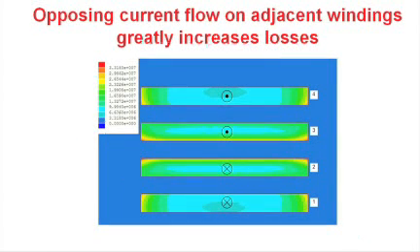However, the situation gets a little worse as you start adding layers of conductors. In this diagram, we're showing two conductors carrying current out of the foil in the top here. On the bottom, we're showing current flow into the foil. And so, as we go through the conductors, we see that the current distribution is different. This outer conductor here on the bottom is just like our two opposing current conductors, and this current is drawn to the surface of the conductor.